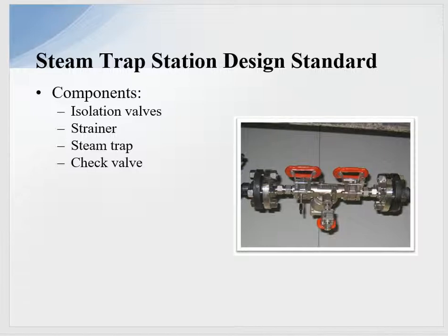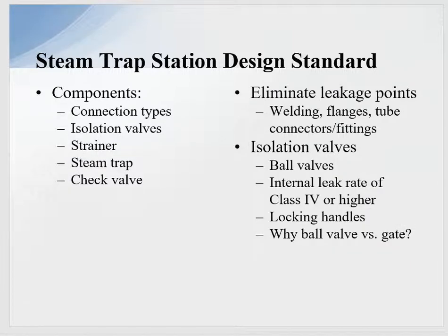One of the things when putting in a steam trap station that we have to be aware of is the elimination of leak points. I want to do whatever I can to get rid of leak points. I'm going to use welding as much as possible — the welder has to be certified to do the weld per B31.1 or whatever code compliance you might be under. The second thing is I'll use flanges, and people say to me, flanges leak. Flanges do not leak — people make flanges leak.